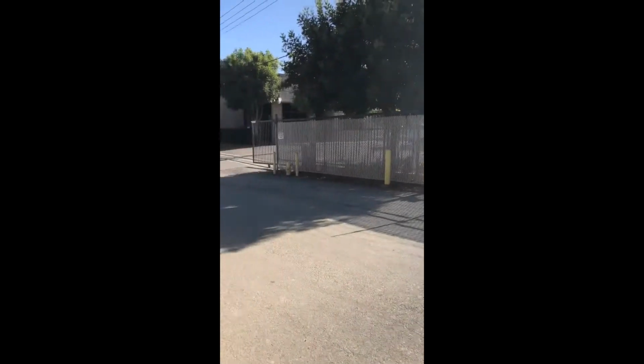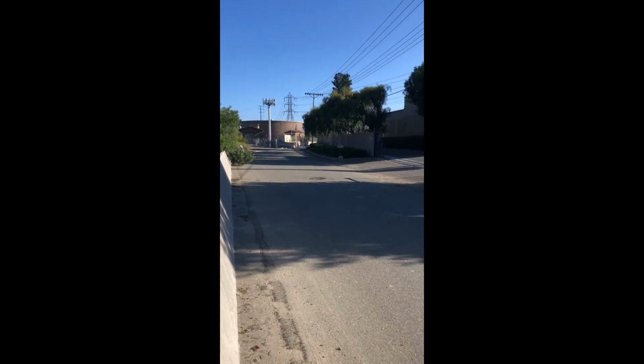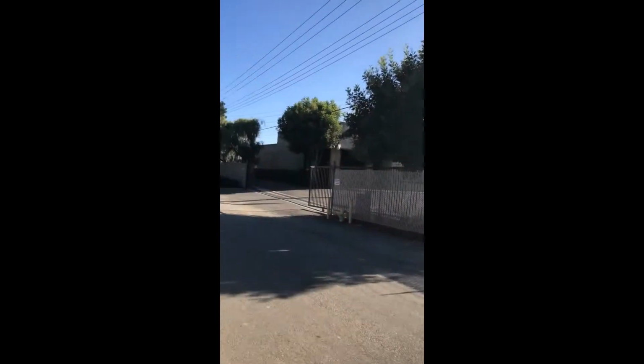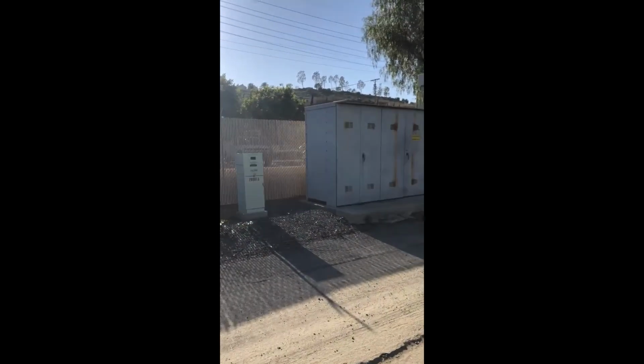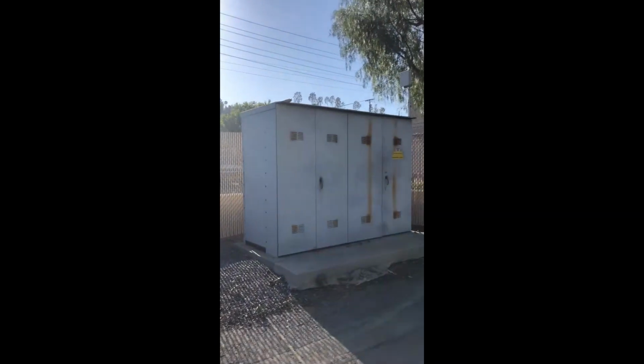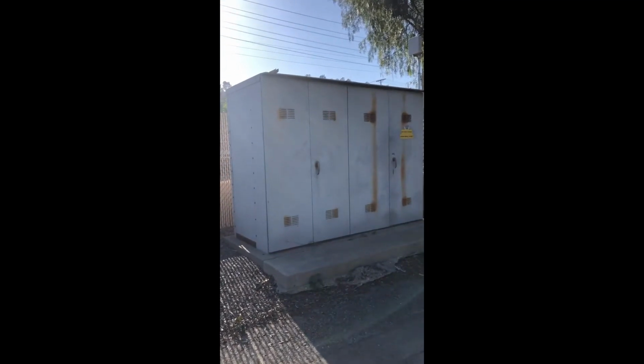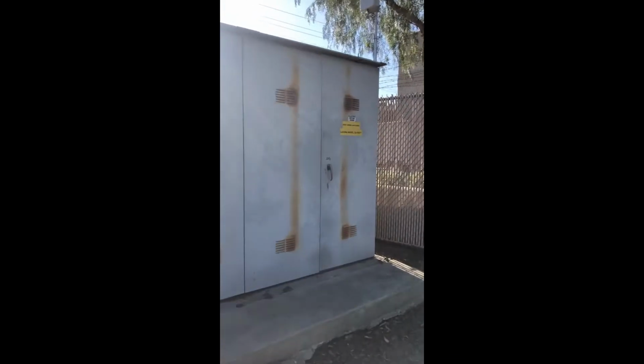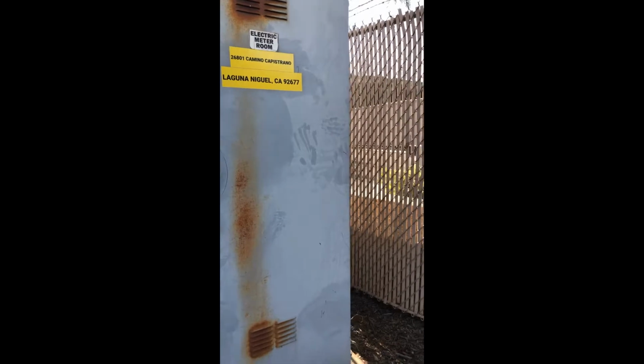All right, so to give you a little bit of perspective, I'm out on the street now, over by the freeway. There's that big storage tank that I referred to. And here is where the power comes in, the power poles. There is the olive green service transformer. This is the transformer for the facility. I believe it's a 12K down to 480 volt. Comes over to this service enclosure. From there, as you can see, it says SDG&E, but from this point on, it belongs to us, and it goes underground.